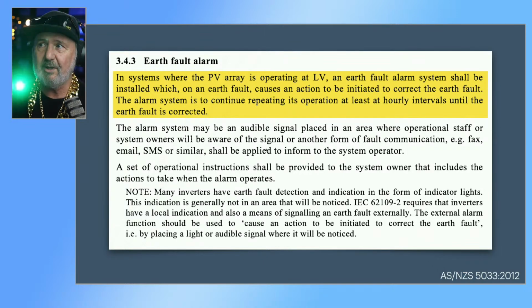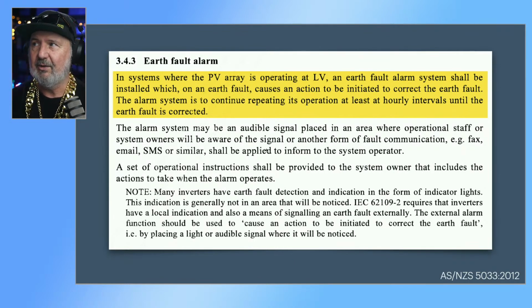So as it says, in systems where the PV array is operating at LV, and LV is defined in 3000 as above 120 volts DC, so anything over 120 volts DC, an earth fault alarm system shall be installed. So shall means mandatory to comply. On an earth fault, it causes an action to be initiated to correct the earth fault. So what does that mean? Well, probably an alarm. The alarm is to continue repeating its operation at least at hourly intervals until the fault is corrected. Or it might be the alarm might be visual.